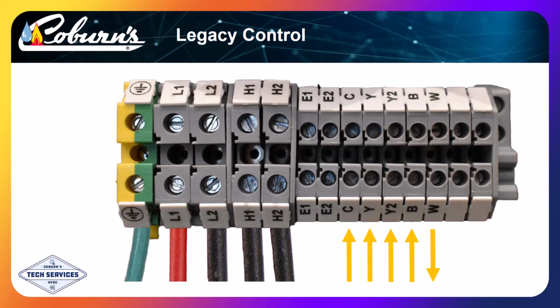The RD17 does not have to be connected communicating. It can also be connected legacy using 5 control wires. We bring a common, Y1, Y2, B, which is the reversing valve, and supplemental heat output W. This mode provides no modulation and is simply 2 stages of operation in cooling or heating.